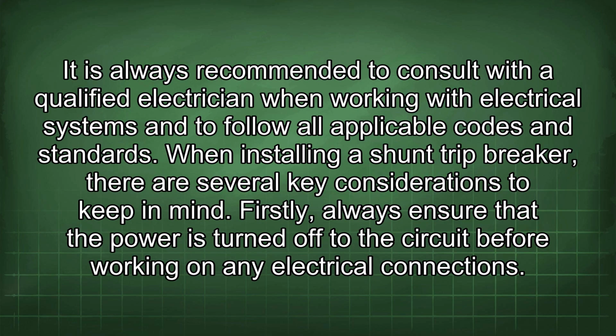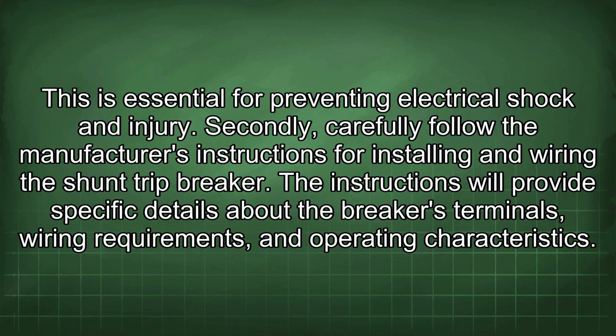When installing a shunt trip breaker, there are several key considerations to keep in mind. Firstly, always ensure that the power is turned off to the circuit before working on any electrical connections. This is essential for preventing electrical shock and injury. Secondly, carefully follow the manufacturer's instructions for installing and wiring the shunt trip breaker. The instructions will provide specific details about the breaker's terminals, wiring requirements, and operating characteristics.